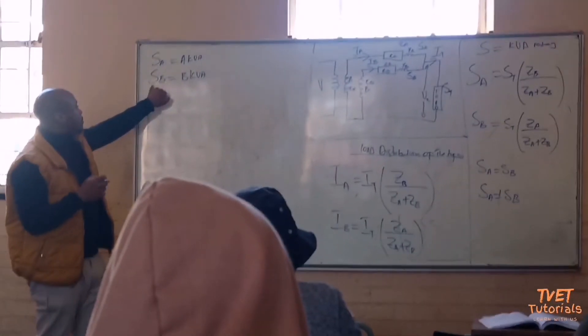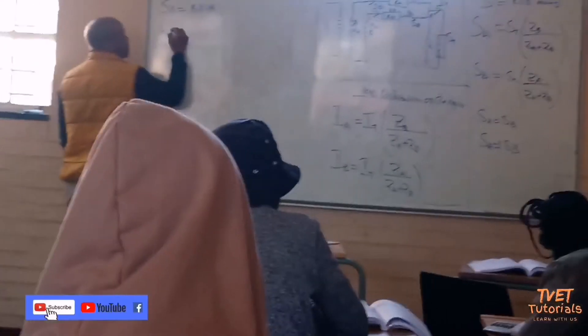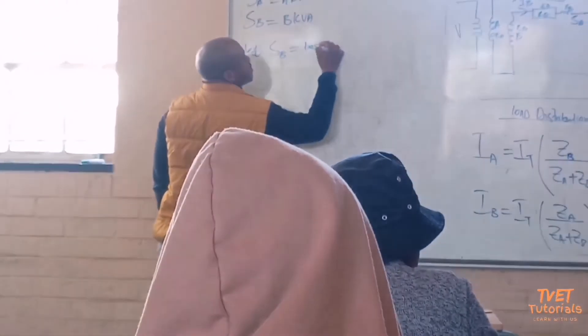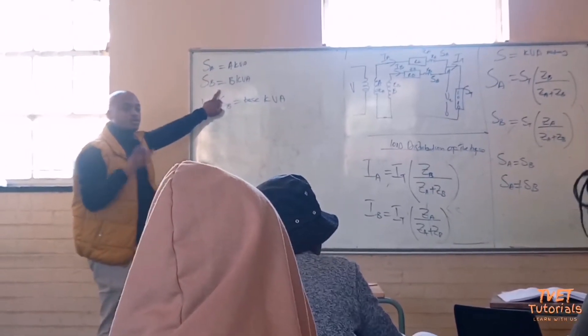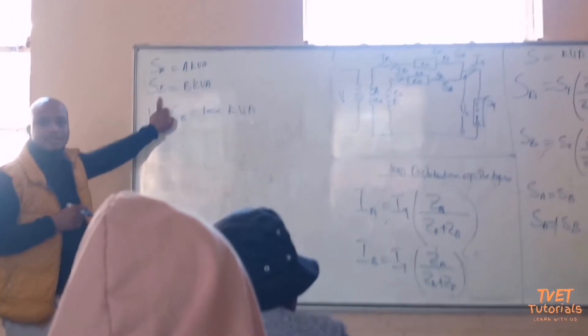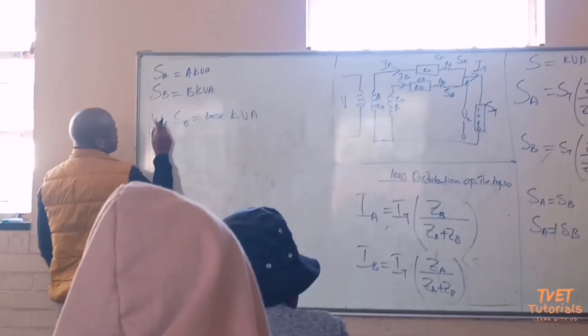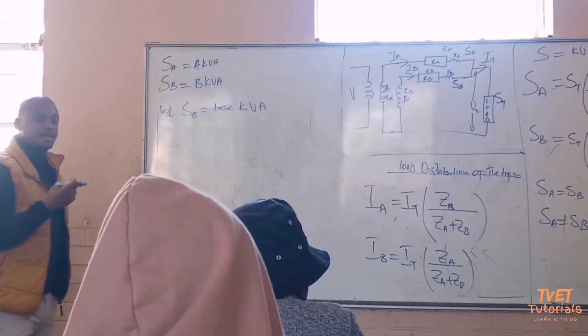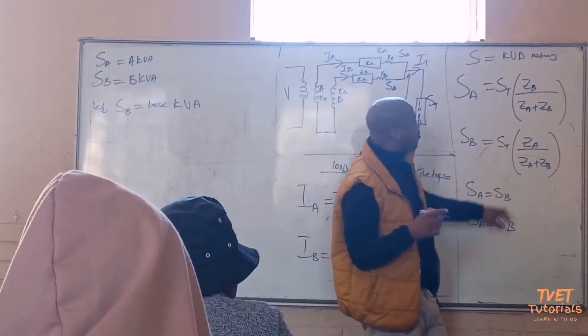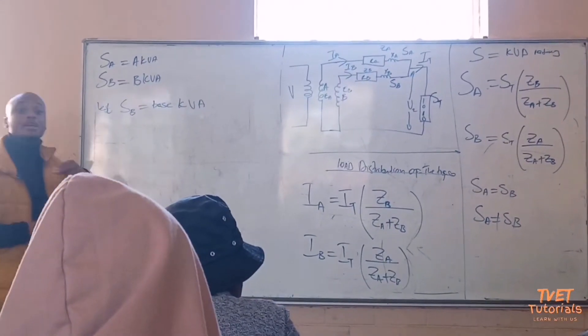For example, if S from Machine B is greater than S from Machine A, you let S from Machine B be equal to your base KVA. Always choose the one that has the biggest KVA. Once you have chosen the base KVA, you then calculate a new ZB and a new ZA so that the condition of impedance equality is met.